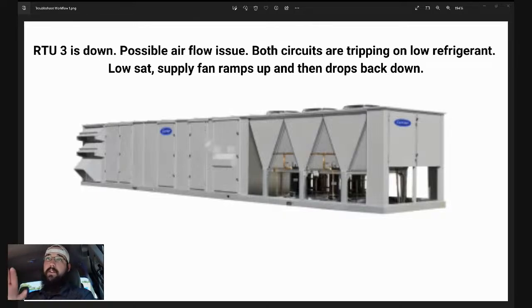It was going from just a couple of degrees of saturation and then was spiking back up to, I forget, I think it was in the 20s, I believe. So as it was running, and then he had very similar results when he brought in the second compressor. And if I'm not mistaken, he was running low saturations throughout that whole duration. Because one of the first things he did when he got there was he powered the unit back up. I think that's what it was. It was down. He powered it up, and it ran fine for 30 minutes, and then tripped on the low saturation alarms that he was seeing.